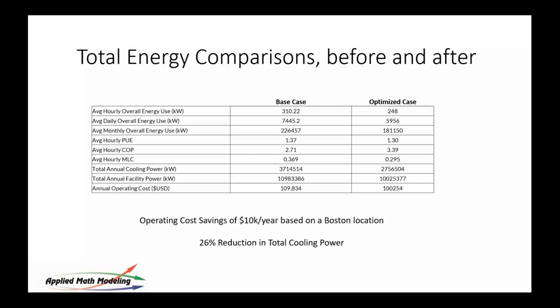From what source you get the weather? I did that already. What are the energy consumption of components in the data center cooling loop? The energy consumption of the components in the loop itself isn't broken out uniquely. We're doing total cooling energy. But the way we get the energy for each of the components is to take a look at its individual curve. As you can imagine, there's a performance curve for every piece of equipment, and we do it every hour. We take a look at the curve, where we are on the curve, and use its efficiency, what we call part load ratio. What is the efficiency of that device as a function of its design center or design point? So it's a ratio. It's called the part load ratio, and we do it for all devices.